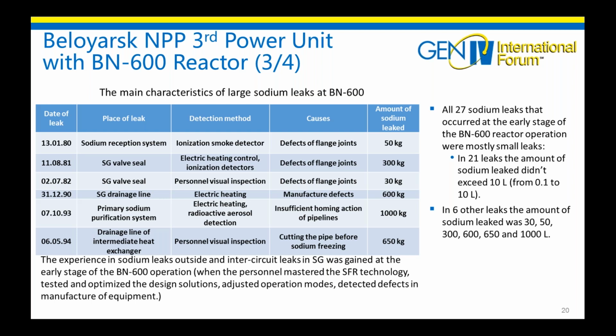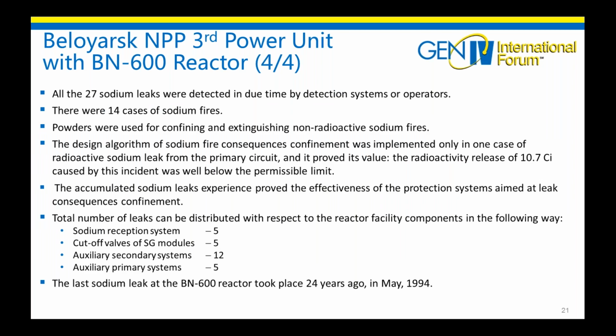As you can see, we have only 1 big leak in the primary sodium system. There were 14 cases of sodium fires. All the 27 sodium leaks were detected in due time by the detection system or operators. Powders were used for confining and extinguishing non-radioactive sodium fires. The design algorithm of sodium fire consequences confinement was implemented only in 1 case of radioactive sodium leak from the primary circuit, and it proved its value. The radioactivity release of 10.7 curie caused by this incident was well below the permissible limit. The accumulated sodium leak experience proved the effectiveness of the protection system aimed at leak consequences confinement.